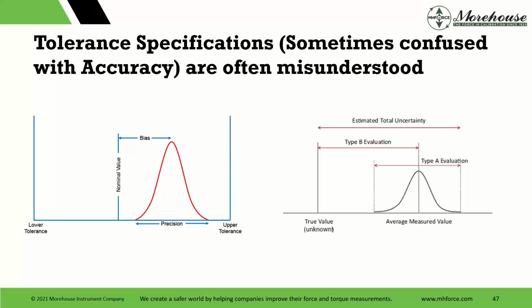Now, the picture on the left, a lot of people see. You have your nominal value, you have your bias. The reason this is here is because if you're a lab that likes everything to read as close to nominal as possible, things drift off on you. And then a lab says it's in tolerance, right? And a lot of the standards are written assuming everything is centered. They hardly ever are.